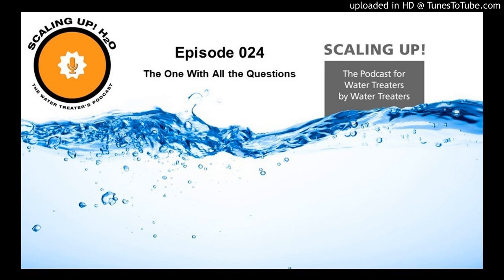Anything above 6 this time, we're going to dissolve calcium carbonate. And anything below 6, we're going to start depositing calcium carbonate. You know, when somebody wants their name on something, they got to put their own spin on it. So that's the spin that we have. And then we have PSI, which stands for either the Puckorius Scaling Index or the Practical Scaling Index.